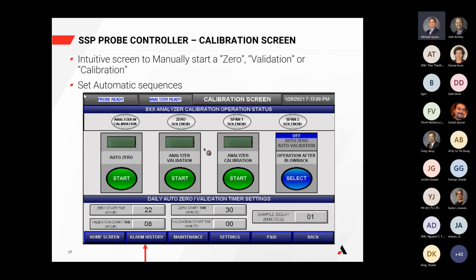Okay, so from here, an end user can manually initiate an auto zero. They can initiate the validation, or they can initiate a full-blown calibration. And in doing so, these little oval shapes up here will be highlighted as things are being actuated or not actuated. You can also adjust when you would want your daily auto zeros and validations to occur. And that's what's showing down here. In this case, this will occur at the 2200 hour, so roughly 10 p.m. in the evening. And that's for the zero start. Again, this is about 10:30 or 22:30 in the evening. We'll see the zero start, and then a validation will be running again.